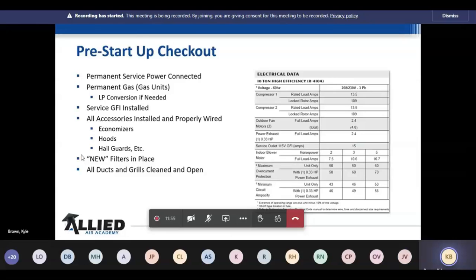And if you got any question on these with the minimum and maximum amps, you'll see with power exhaust, all this other stuff, because that adds to it. And the bigger the unit you get, the more horsepower you're going to have for a power exhaust, especially depending upon which unit you got. Now, a lot of these things I'm talking about today can be applied to K series, Z series, even your splits. So I tried to make sure I kill as many birds with one stone as I can.